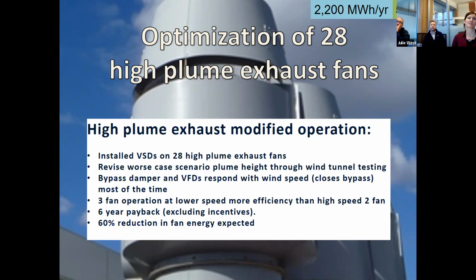Strobics, sorry. Well, how the strobics work is that there is a huge amount of bypass air that is being sucked through them, that's actually not coming from the building at all. It's coming from outdoor air, and it mixes with the laboratory air and ejects at a much higher CFM and height than is needed for our particular campus. So what we were able to do is modulate and close the bypass dampers and reduce the speed that the high plumes are operating at, based off of the sequences that the company that did the wind tunnel testing provided to us.